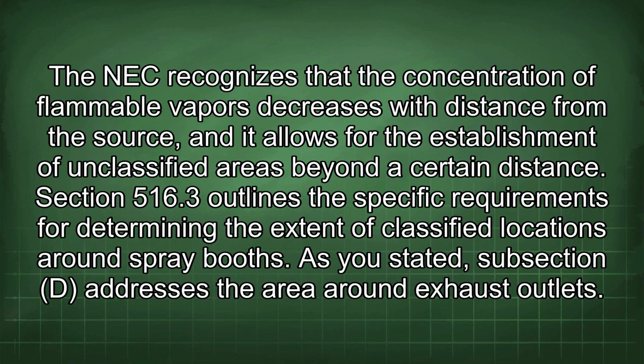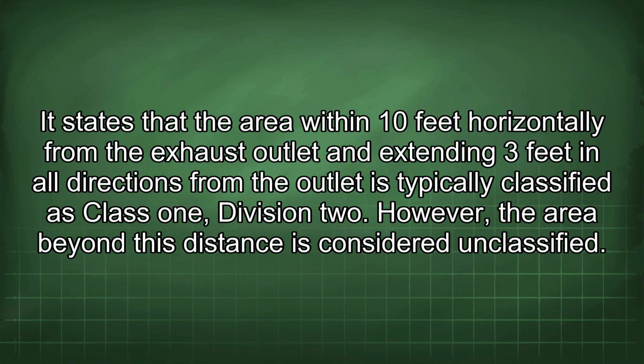The NEC recognizes that the concentration of flammable vapors decreases with distance from the source, and it allows for the establishment of unclassified areas beyond a certain distance. Section 516.3 outlines the specific requirements for determining the extent of classified locations around spray booths. As you stated, subsection D addresses the area around exhaust outlets. It states that the area within 10 feet horizontally from the exhaust outlet and extending 3 feet in all directions from the outlet is typically classified as Class 1, Division 2. However, the area beyond this distance is considered unclassified.